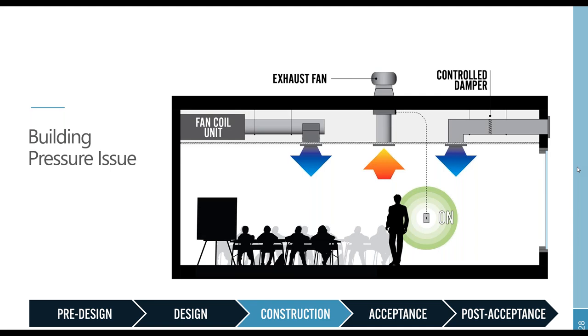So in the end, because of the investigation that we did into something as little as transfer air through a duct, we were able to determine that the contractor had installed the wrong damper, incorrectly installed the damper that they did install, and then got them to make the fix prior to students being in the space to ensure that we can actually get adequate pressurization, comfort, and not have humidity issues by having hot, humid air constantly coming in through this ductwork into the space as well.